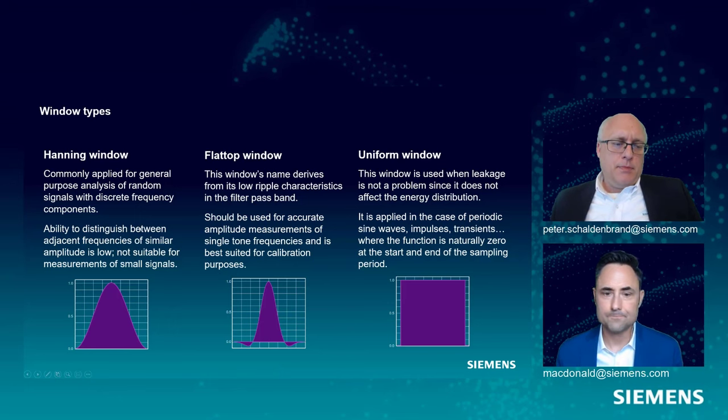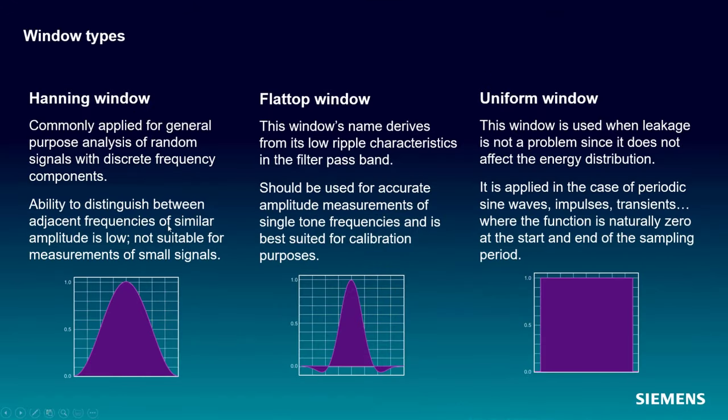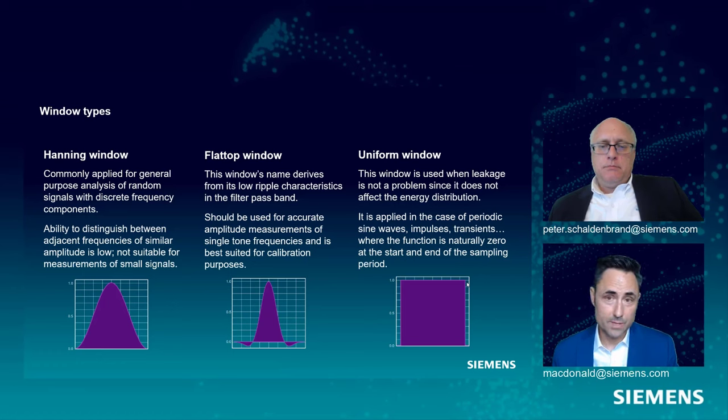This guy is called a Hanning window, nice bell-shaped curve, sort of a generic purpose window. There's also one called the flat top, which is really good at maintaining amplitude accuracy, and so it's often used for calibration. Then there's something called the uniform window, which is essentially a value of one for the whole observation time, so you're applying a uniform window if you don't apply a window. The effect is exactly the same, and so you'd apply a uniform window when you know your signal is going to be zero at the beginning and zero at the end. Again, an impact testing sort of scenario.